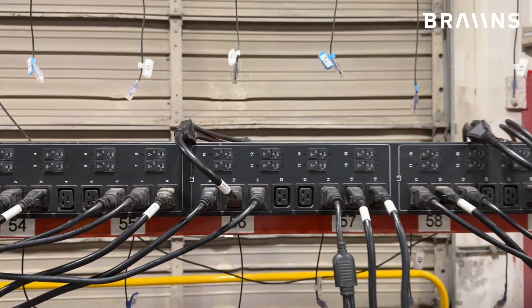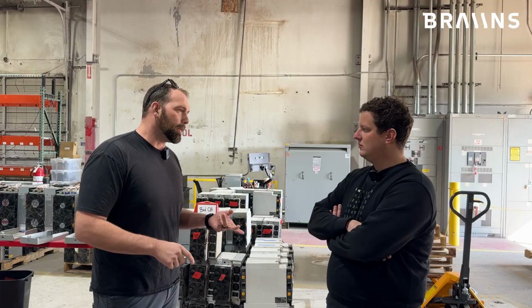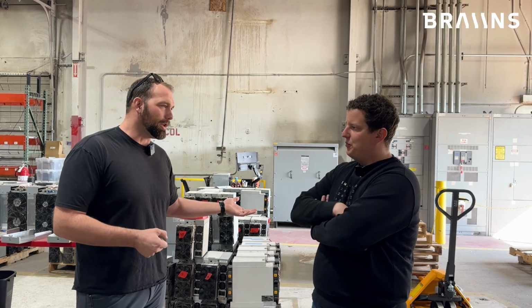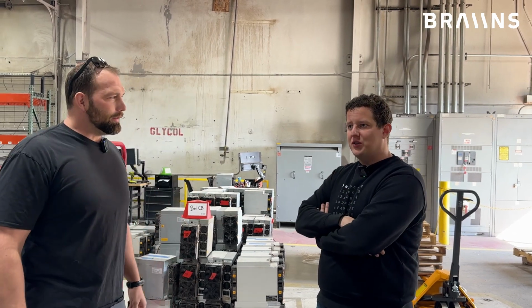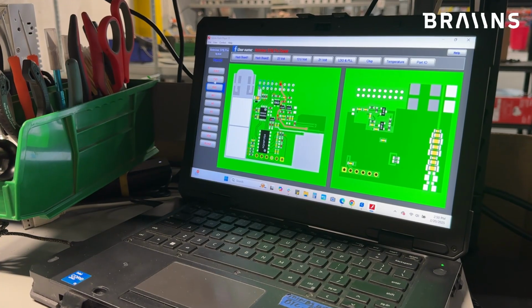So we're doing, with smart PDUs measuring power draw, we get the UI information, we get the pool information, how much power is it drawing. We throw amp clamps on them to verify the smart PDU, important. Because really, a lot of people trust the data in the GUI. We have to remind, it's just an estimate. You have to measure at the wall.